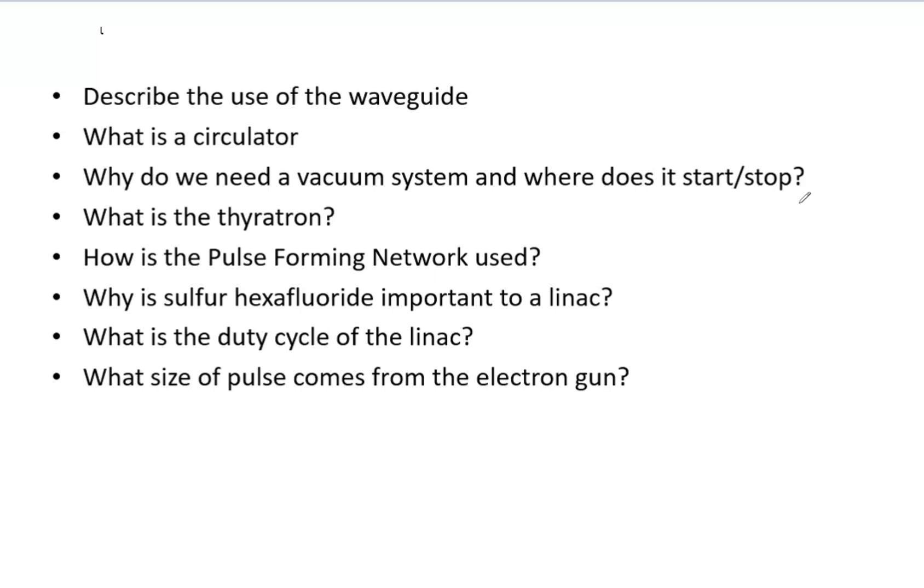Now why is sulfur hexafluoride important to a linac? This is used when waveguides transport amplified microwave power to the accelerator waveguide for injection. It prevents electrical arcing that would ultimately destroy the microwave waveguide structure.